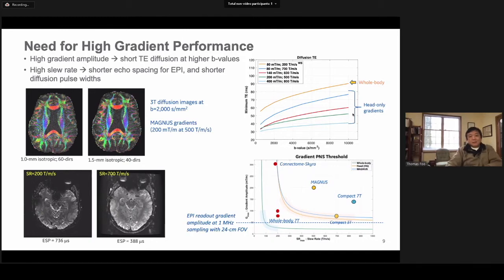Head-only gradients, on the other hand, are able to achieve shorter and shorter TE times. The Magnus system, which we've just recently demonstrated, at 200 millitesla per meter and 500 Tesla per meter per second, is able to reduce the TE times by more than half, achieving roughly between 2 and 2.5 times the SNR. This allows us to go to smaller voxel sizes. Here is a comparison between a 1.5 millimeter isotropic acquisition versus a 1 millimeter isotropic acquisition.